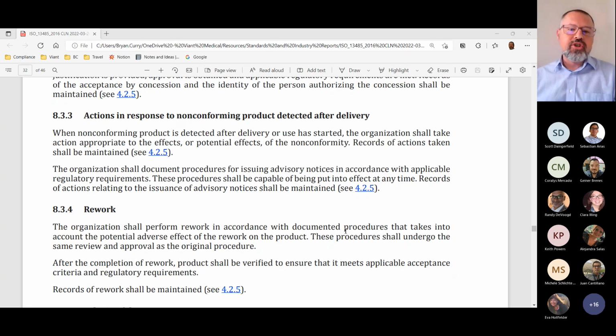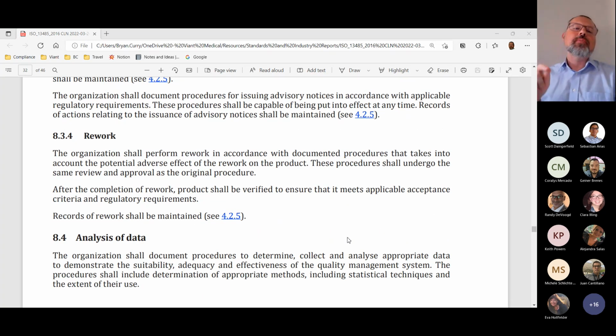Okay, and then there is a specific section under the nonconformance clause around rework. And it talks about how when you perform rework, you should do it in accordance with documented procedures for how you do rework, and that you have to take into account the potential negative impacts or effects of the rework steps themselves on the intended performance of the product. So if your rework introduces other risks or causes the device to become non-conforming in some other fashion, you have to capture that and provide it as part of your assessment and rationale as to why the rework instructions are okay, and it is still worth reworking the product.